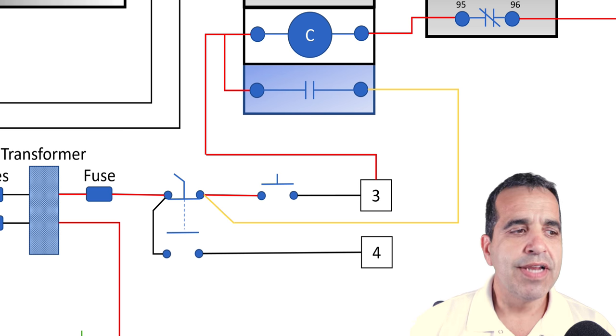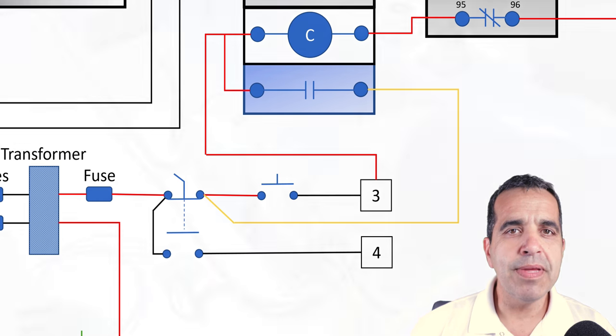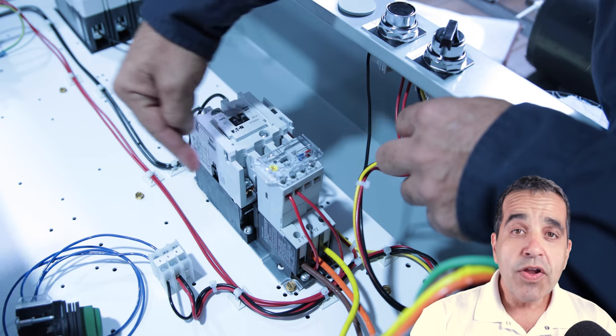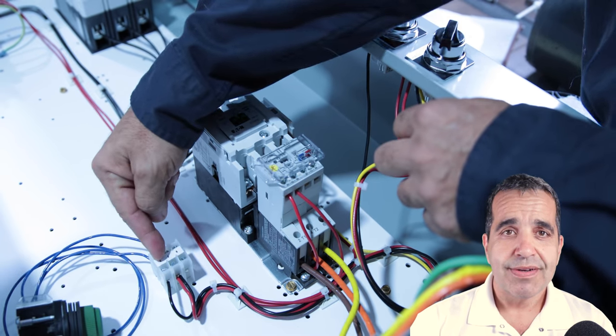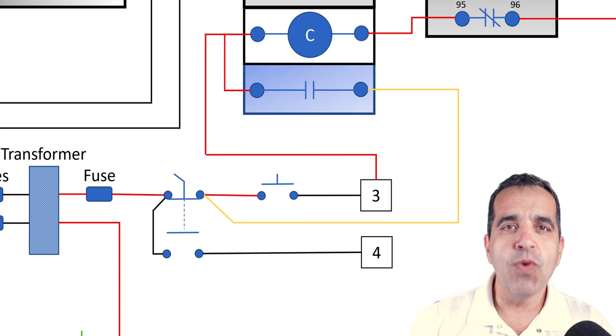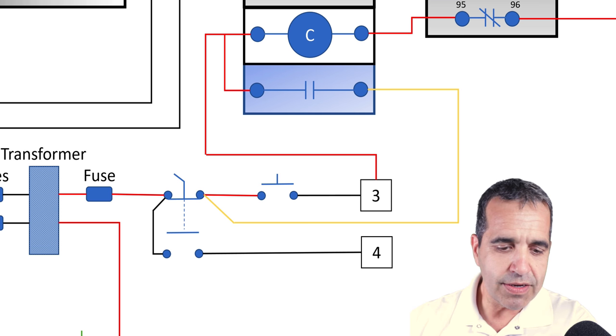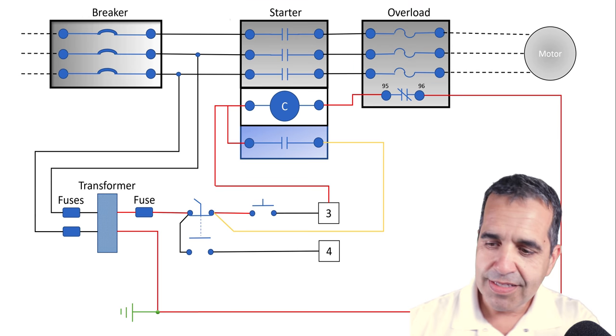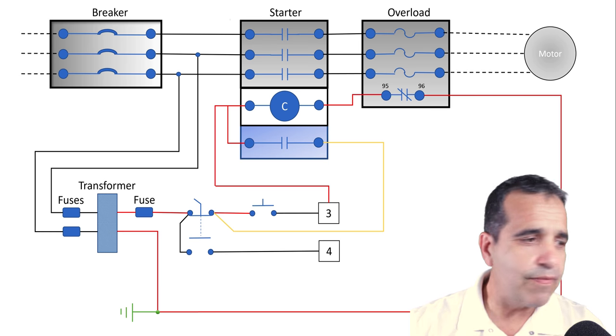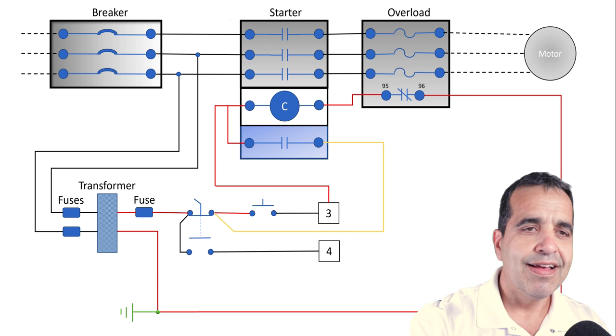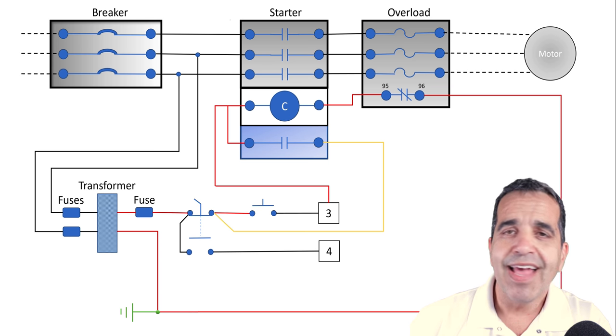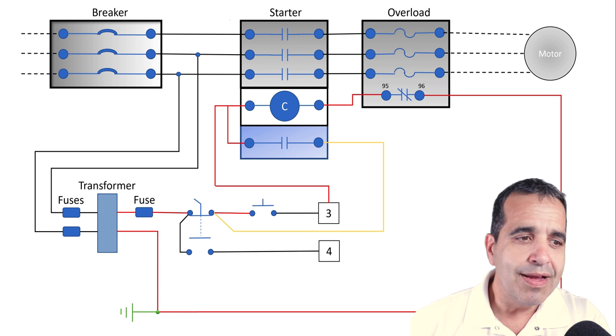Finally, we have another wire coming from the auto side of our switch, and it is feeding terminal block number four in our pump panel. Now typically what you'll do here is you'll feed some kind of field device—it could be a float, it could be a timer, anything like that.